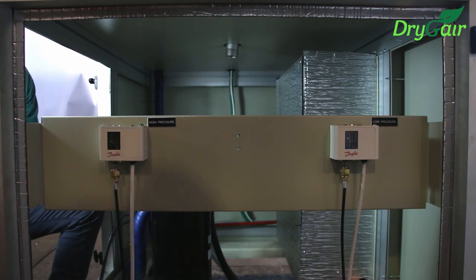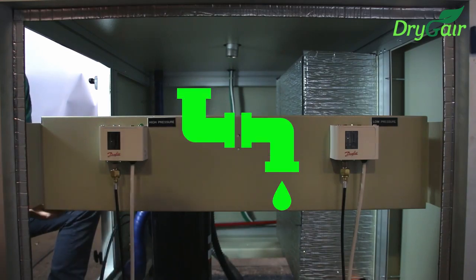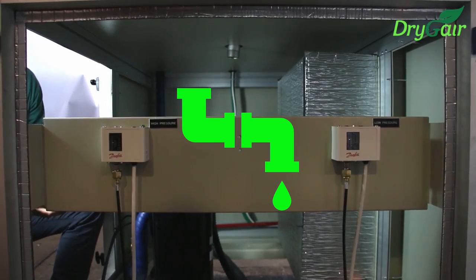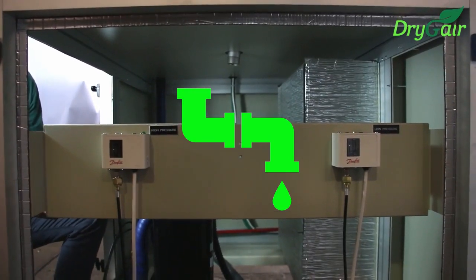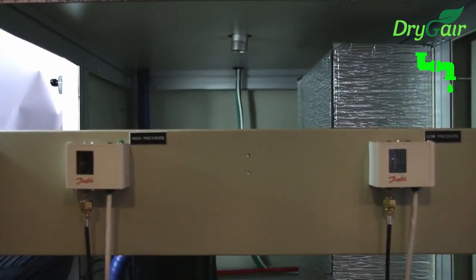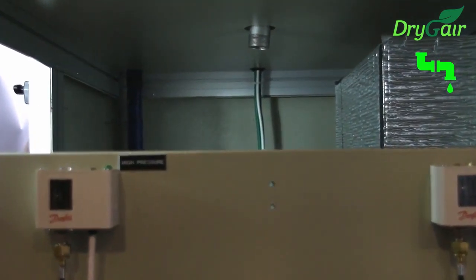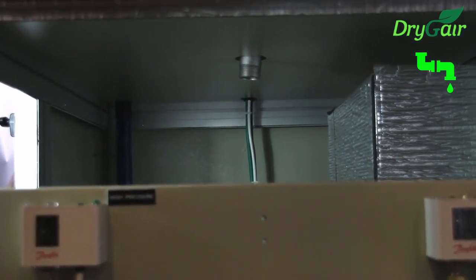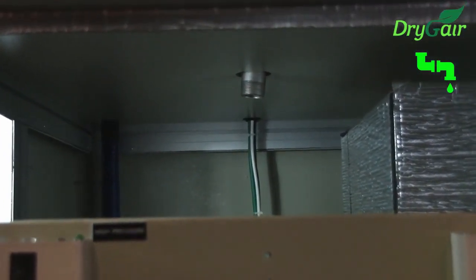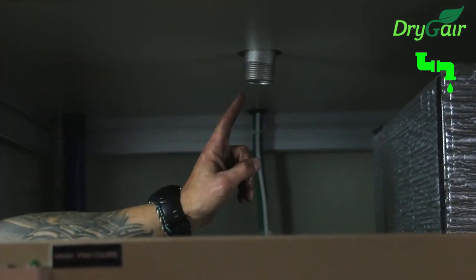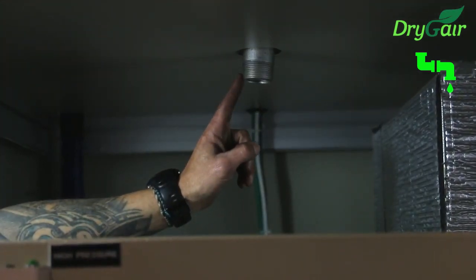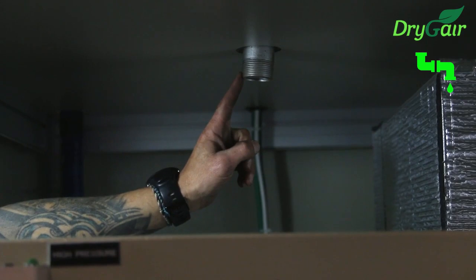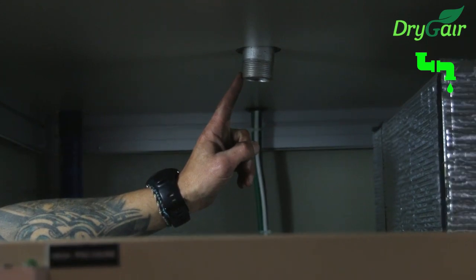The next step is to connect the water drain pipe to the unit. During the unit's operation, water is condensed and needs to be removed from the unit. In some environments, depending on the air temperature and humidity, this may be a large quantity of water. To prevent water accumulation, the water drain pipe should be connected by a plumber to a drainage line leading outside the greenhouse or to any other place that the water can be collected, such as a container.